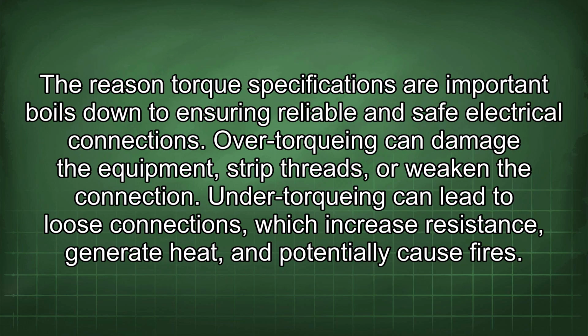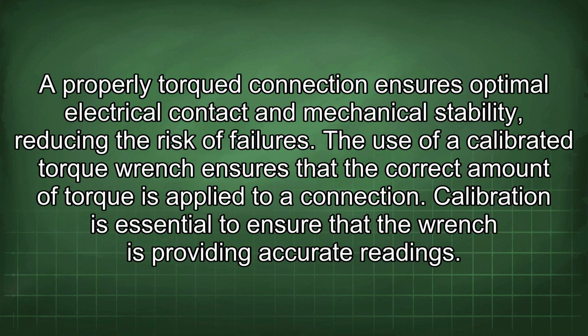The reason torque specifications are important boils down to ensuring reliable and safe electrical connections. Over-torquing can damage the equipment, strip threads, or weaken the connection. Under-torquing can lead to loose connections, which increase resistance, generate heat, and potentially cause fires. A properly torqued connection ensures optimal electrical contact and mechanical stability, reducing the risk of failures.